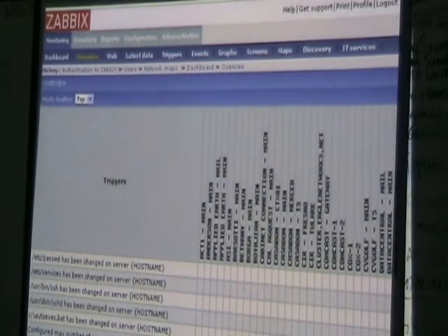Unfortunately, a couple months ago the system wasn't taking that into effect, and it was raining outside and sucking in air from the outside, and we ended up having our servers go down because there was corrosion on the PCI cards.